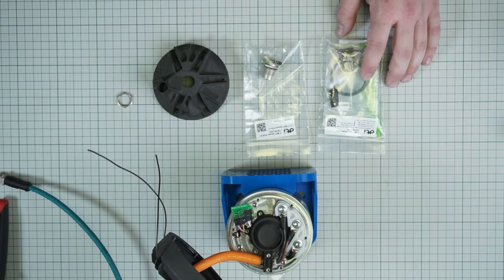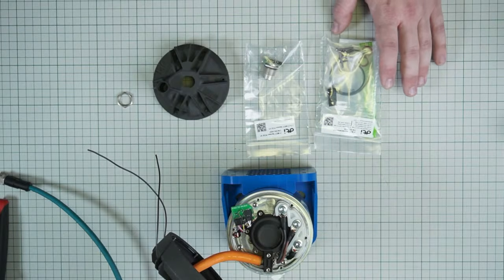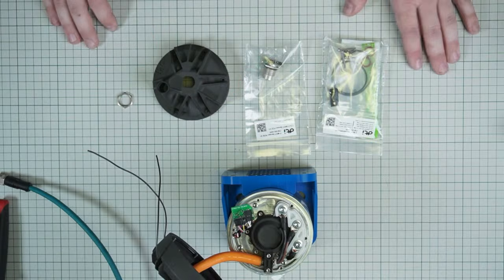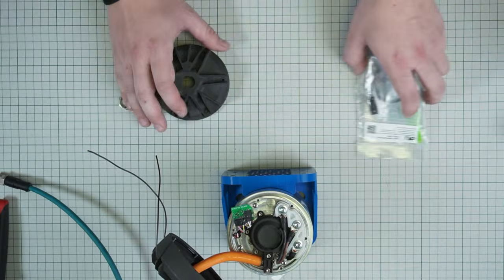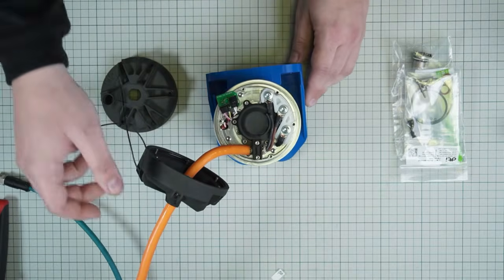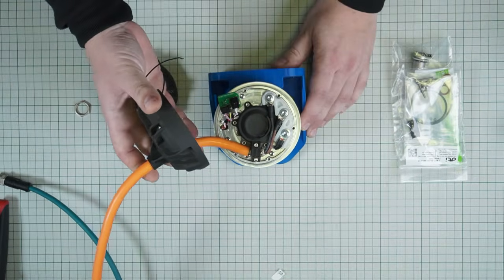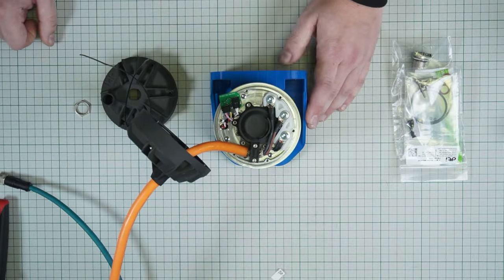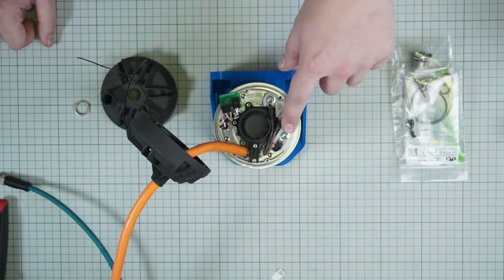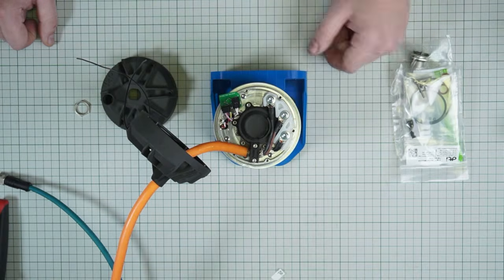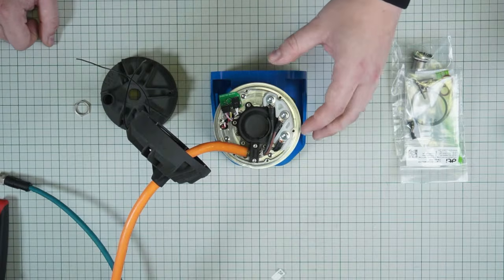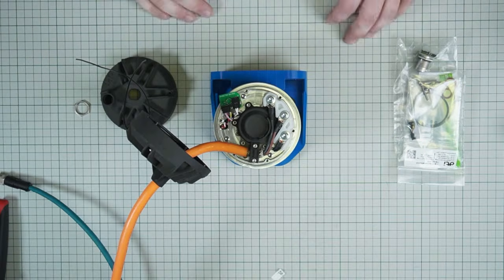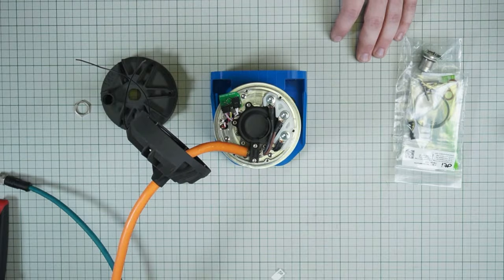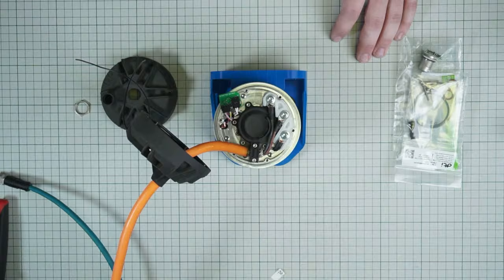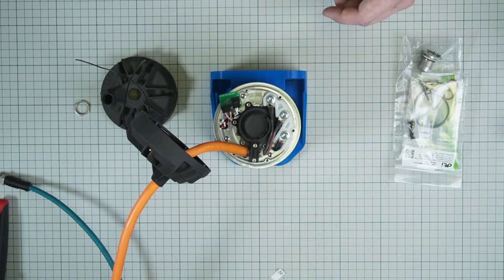I would also like to mention that it's very important to use proper tightening torques across all the tightenings, for the motor bolts. If you don't properly follow the guidance, you can perish the O-rings on the end caps, and in a worst case situation, you can even damage the AC connection. Technically, this PCB consists of connectors for both connections, and you can damage it if you are not properly following the guidance on the torque specs. So it's very important to read through the application manual and check the torque specs of the motor.